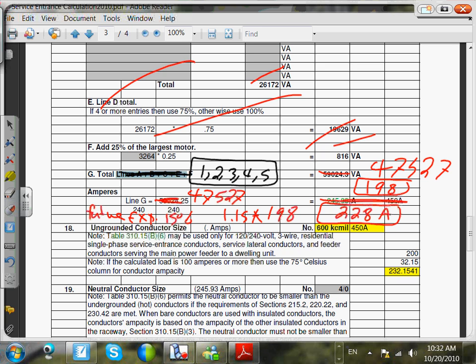Okay. So if we threw the 240 out when we were doing our calculations, where are we dividing by 240 and not 120? Very good question. Because the load is going to be balanced between the two phases, right? Half of these 120, or close to half, will be in hot 1. The other half will be in hot 2. You're not going to put all of them in hot 1, are you? You can't, even if you want to. If you start loading them on any side, you start balancing. Yes, they're 120, but they're balanced between the two of them. Okay, so 228, good question.